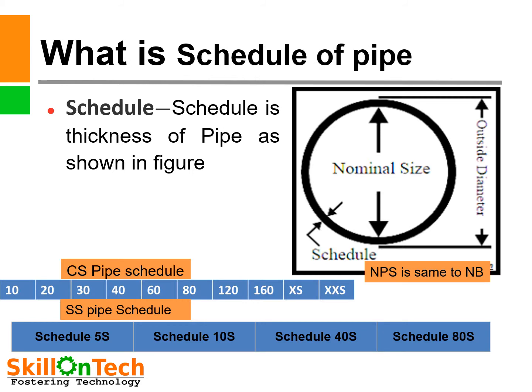What is schedule of pipe? We must know about schedule because it is very important. Schedule is the thickness of pipe, as shown in the figure. Pipes are available in various schedules. CS pipe schedules are available in schedule 10, 20, 30, 40, 60, 80, 120, 160, extra strong, and extra extra strong. As schedule increases, the thickness of the pipe increases.